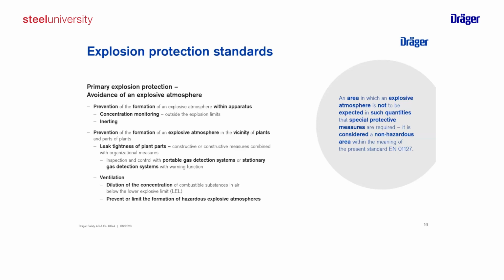And then in these cases, the standard, which is the EN 1127, defines an area in which an explosive atmosphere is not to be expected in such quantities that special protective measures are required. It's considered a non-hazardous area. So it means we have nothing to do. We need to document it, we need to consider it in our risk analysis, but we are done. In all other cases, we have to consider this and go to the next step.